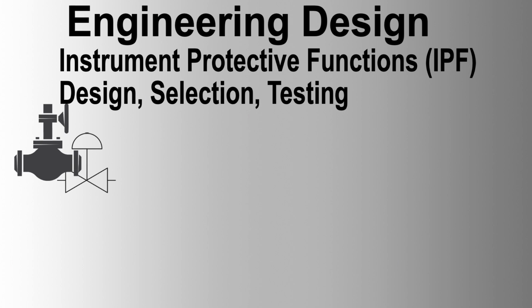Analog inputs. The IPS should be able to receive the following types of input signals: 4-20 mA non-earthed passive 24-volt DC 2-wire, 4-20 mA non-earthed active 24-volt DC 2-wire, 3 or 4-wire platinum resistance temperature detector RTD, pulse frequency type, K, J, or B thermocouples. The requisition should indicate to which signals square root extraction is applicable.